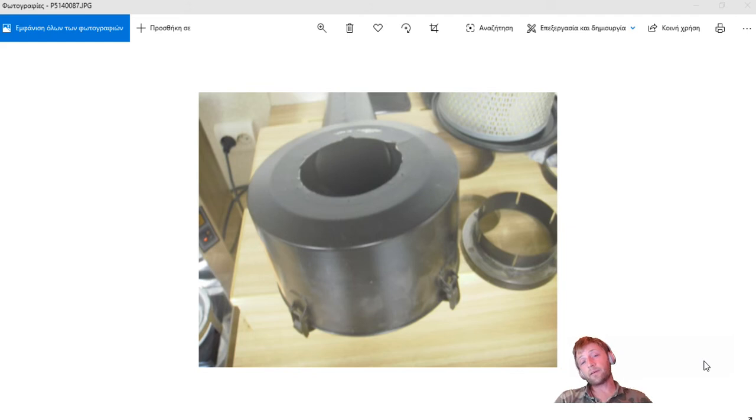So what I am thinking happened here, one of the problems, is that compressors are really shaky. That is true. So vibration is one of the factors that can be considered here. We have excess vibration, and probably also excessive tightening of such parts. So if we have our equipment and one bolt here, let's say, which holds all this filter with one kind of lock here, when you screw and tighten this screw, all this system will be compressed inside.